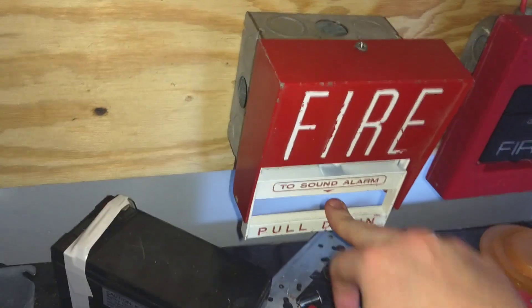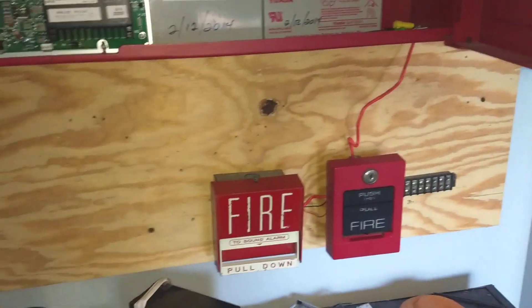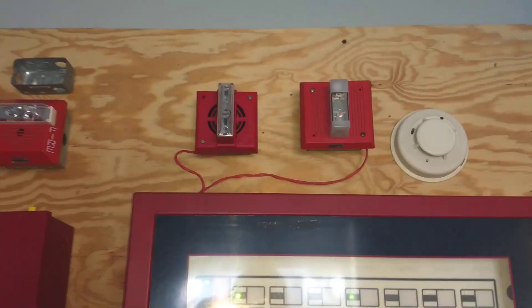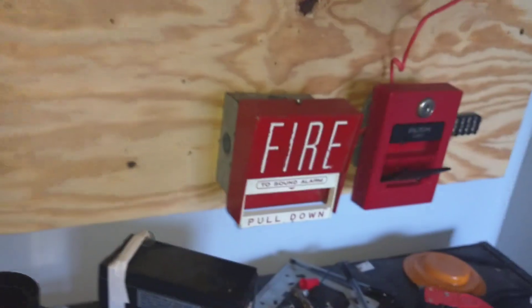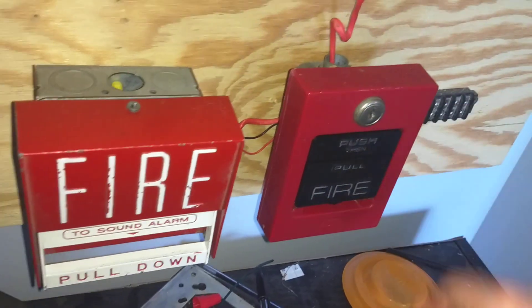Watch, let's open up the BG-6 again and see if it does it — let's pull it again. Okay. That's a cool feature. So that's interesting. Most newer panels don't have that feature, but I guess it's kind of cool. So now let's do the ADT pull station. Here we go — push in and pull down.